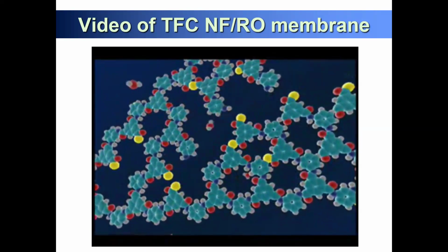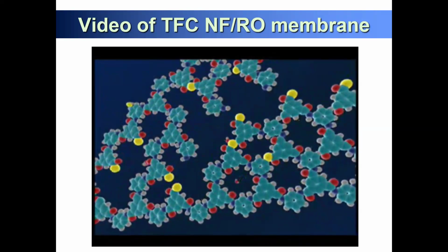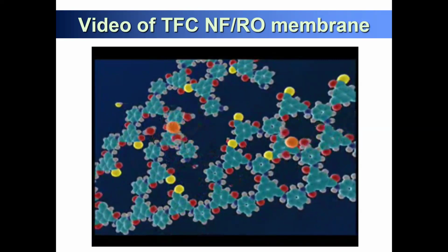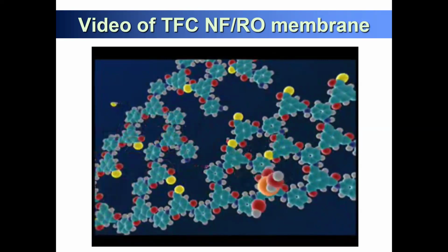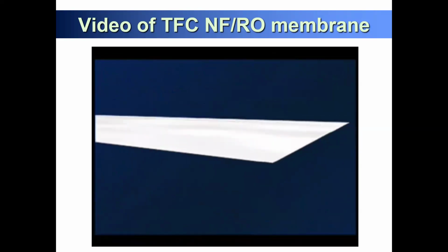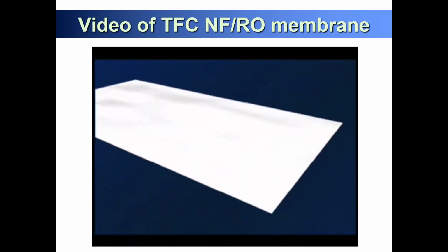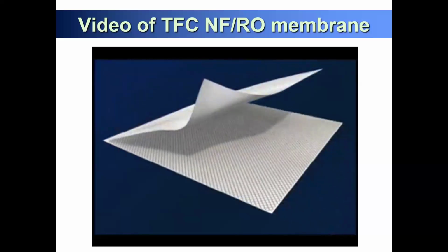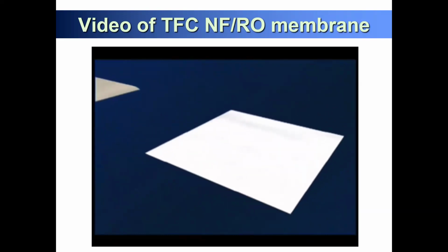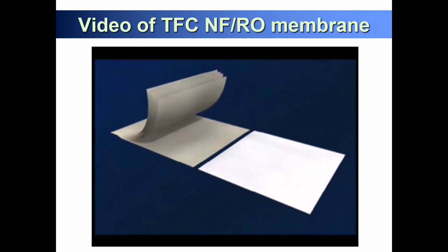Hydranautics manufacturing procedure enables independent optimization of the distinct properties of the membrane support and salt-rejecting skin. The combination of these three layers makes a durable membrane flat sheet that is used in each spiral wound element. The membrane flat sheet is then combined with a sheet of feed channel spacer.